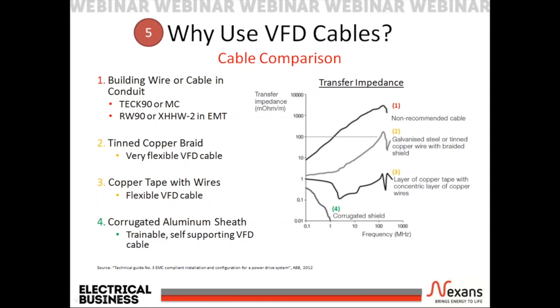In one of ABB's technical documents, they discuss this idea of transfer impedance and set up a maximum acceptance impedance of 100 milliohms per meter over a wide frequency range, from a few hertz to well beyond 100 megahertz. If a cable's transfer impedance is above this threshold, then it is unacceptable for use as a VFD cable.